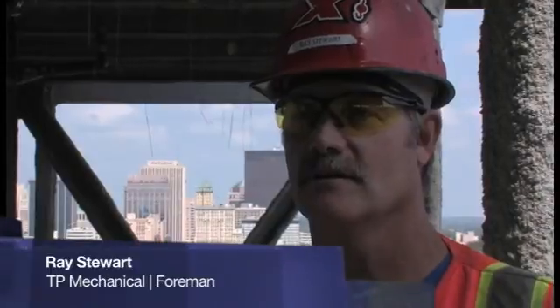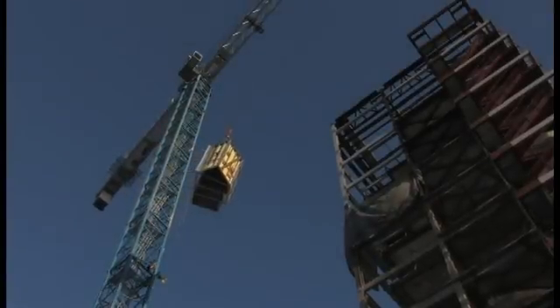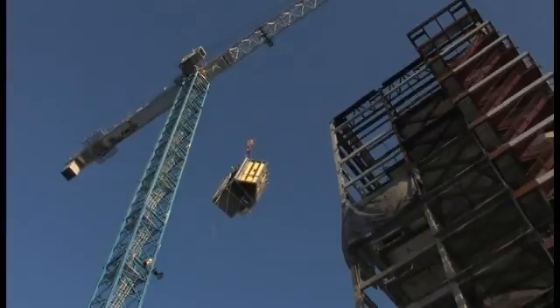Soldered on the ground and put in the rack, so there's not as much chance for a leak, there's not as much chance of getting dirt and rocks and insulation in it, as there would be if we brought it up here and set it on the ground. It's already in the rack, already been taped up before it got here. It was easier to track the circuits and the conduits — everything was able to be labeled, so that when it's up in the air, all we have to do in the field is look up and say, oh yeah, I know what wires go in that conduit.